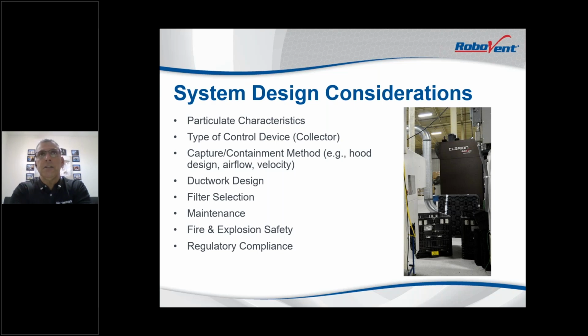Duct design. There's two schools of thought on duct design. One is maintaining a high enough velocity to convey that particulate from the process to the collector. And there's another school of thought that says run that ductwork velocity at a slow enough velocity where it's going to condense in the walls of the ductwork and potentially flow back to your process to reclaim that fluid, or perhaps pitch the ductwork so it collects back into the control device, the collector, and deal with it that way through a drain or some other methodology.